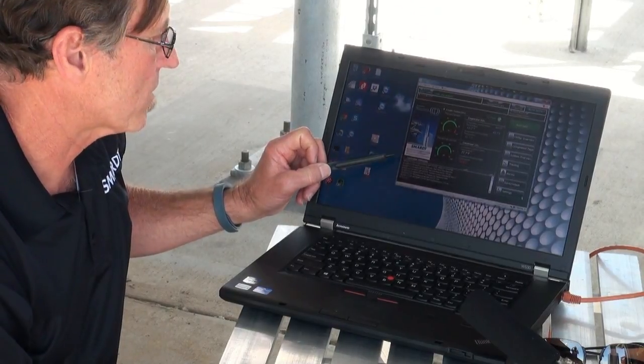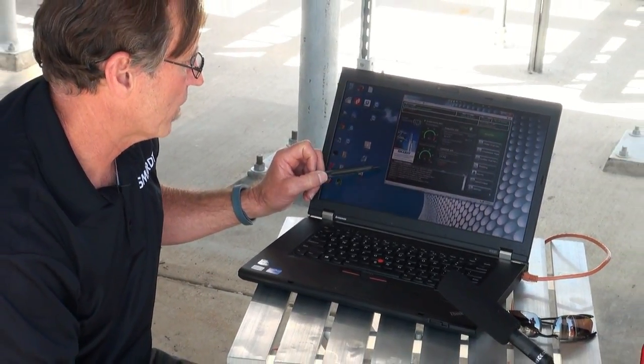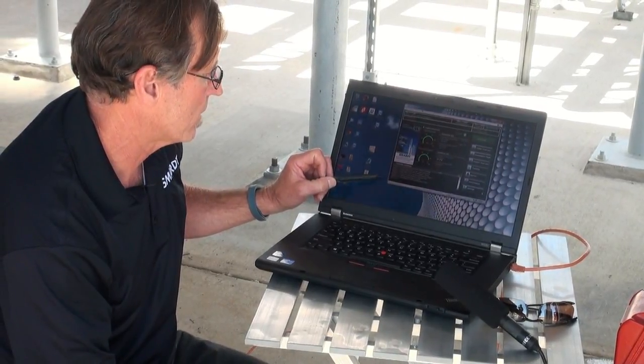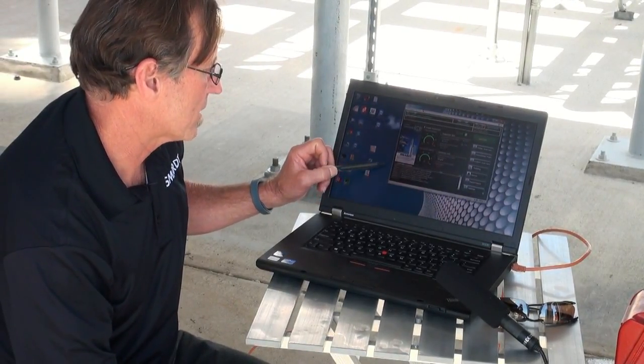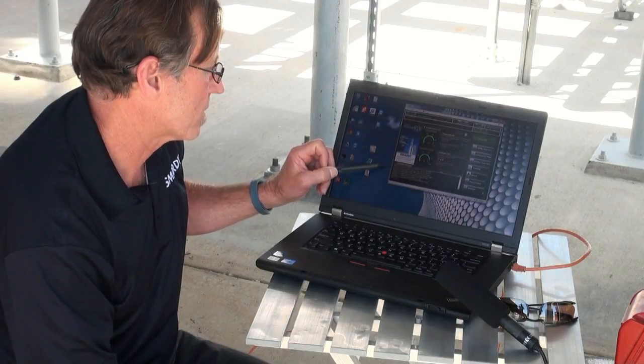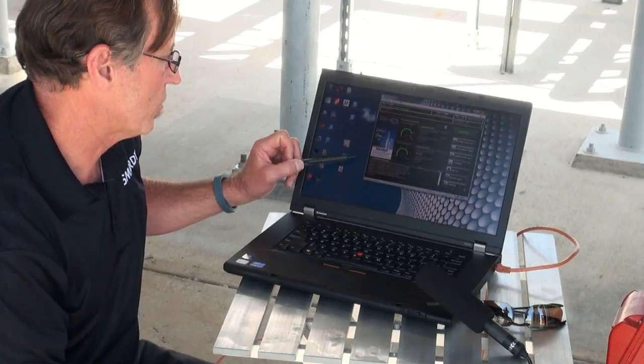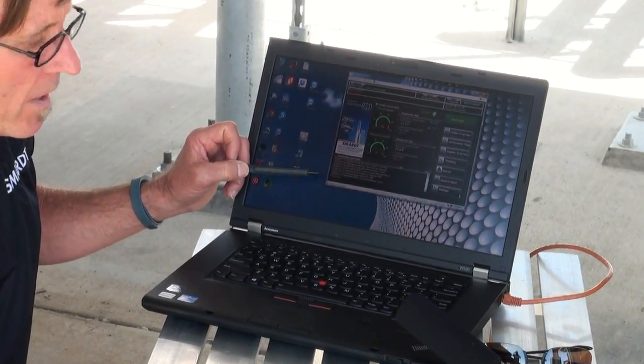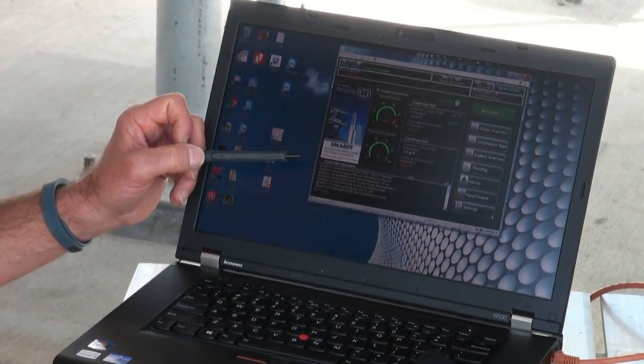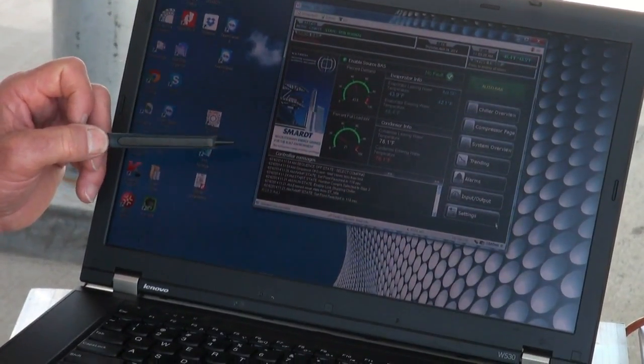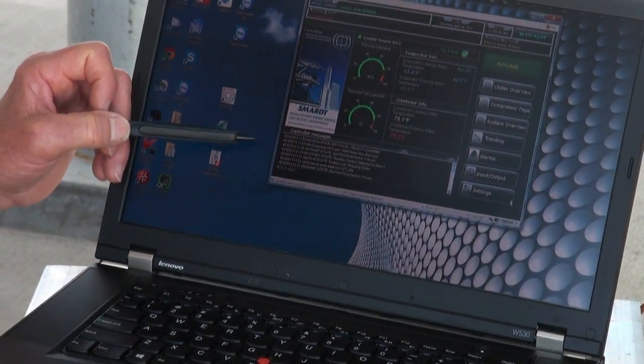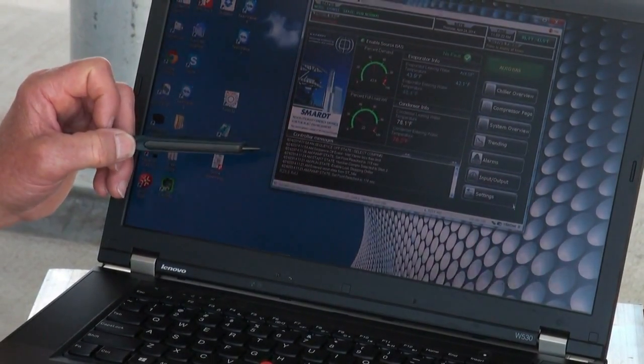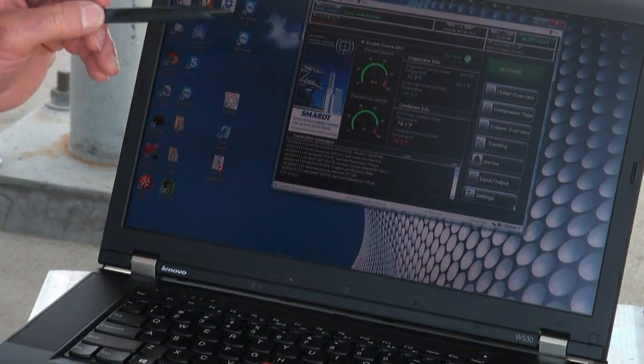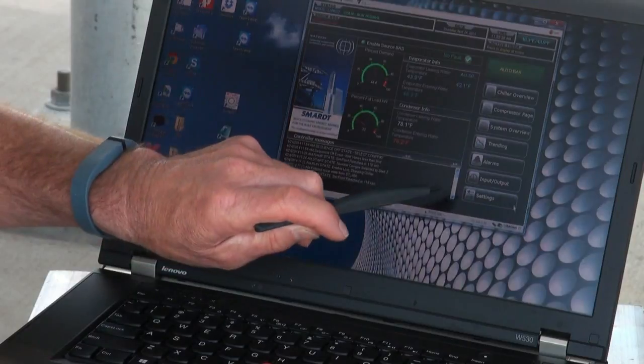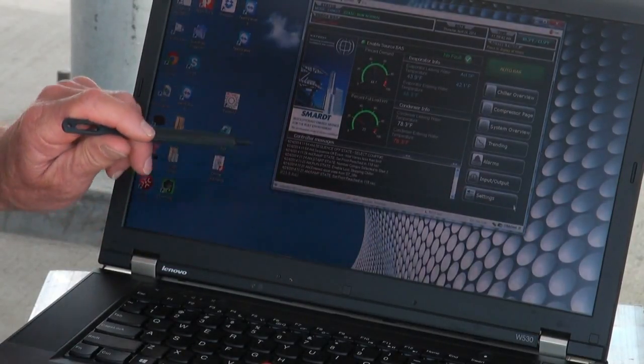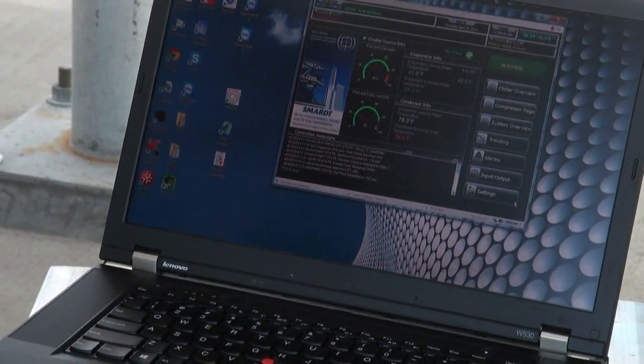Down below, we've got controller messages on this page. Very helpful when you're trying to understand the logic of the controller. Our last event was sequence off state compressor number 2. Every move it makes, it'll come up with a message. So if you're curious where we're at with the controller, what stage we're in, we can get some clue or hint of the thinking of the controller. That's a nice feature. And then of course you can scroll down and see what happened previously.